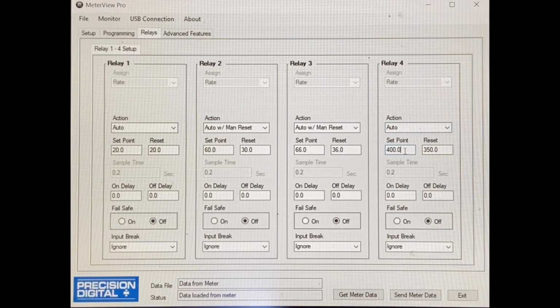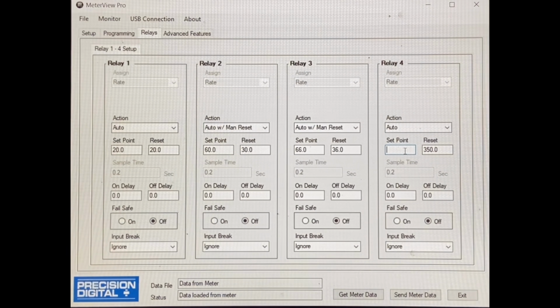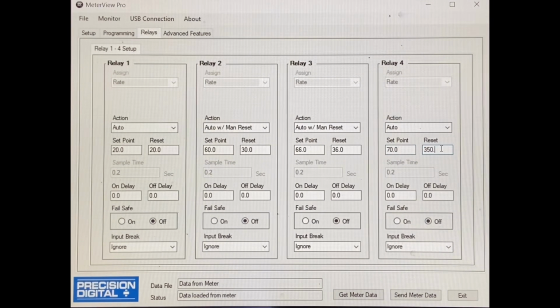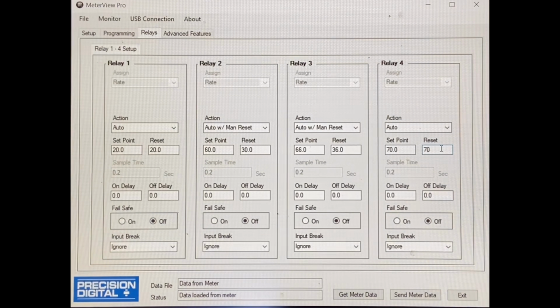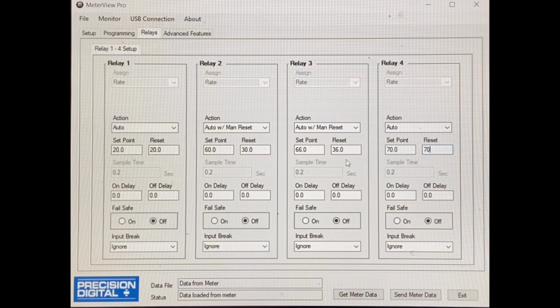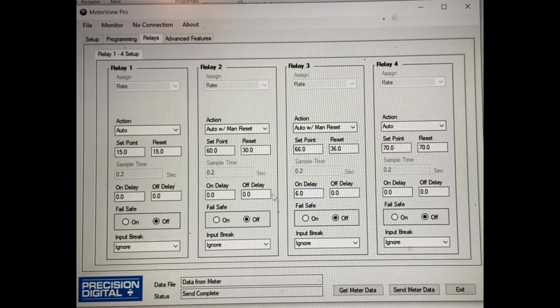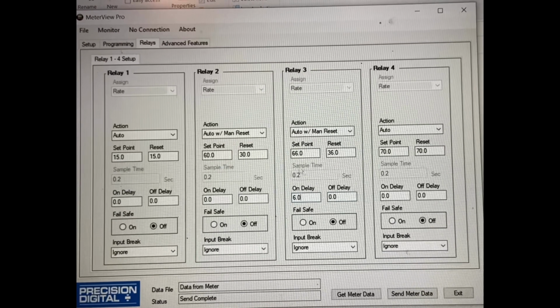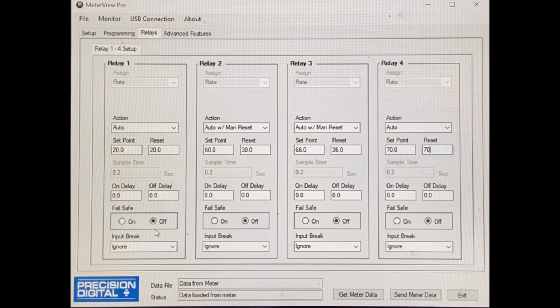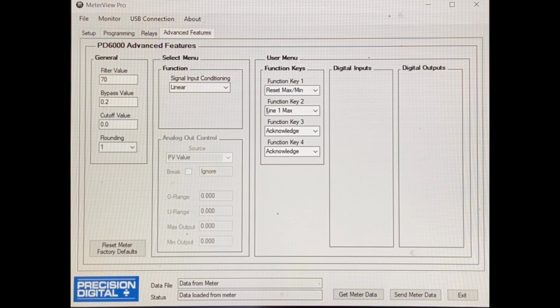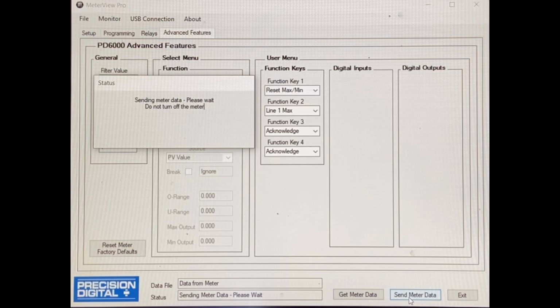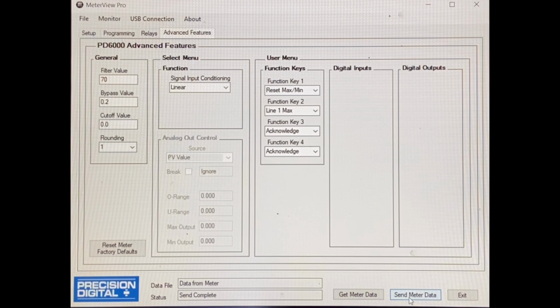In terms of relay 4, that is our transfer relay, and that used to also be a single float, so it's going to act the same as relay 1 and the low level. It's the same idea, it's just a single float, so we do not need that set and reset, we just need on and off. I also added a time delay to relay 3. I actually added this later, I forgot to do that. That is the lag relay, and I want a time delay so that if the power ever cycles, both pumps don't turn on at the exact same time and trip the main breaker, because at some stations that's an issue.